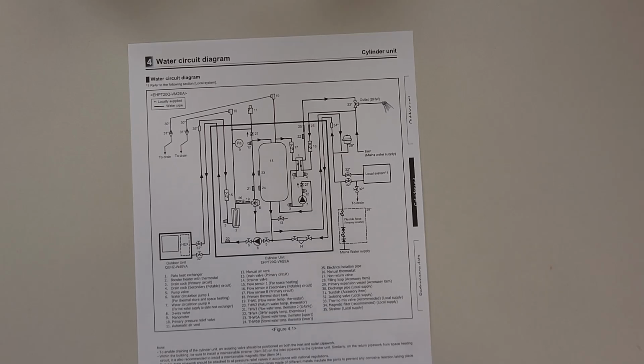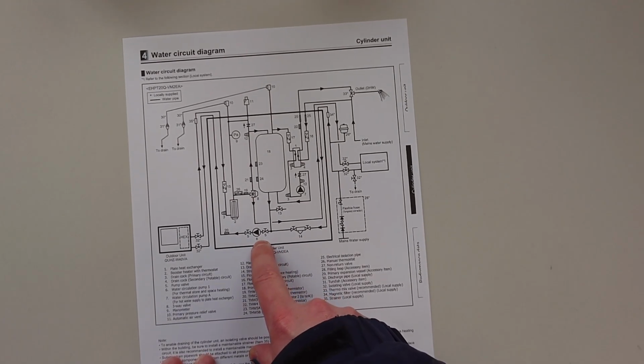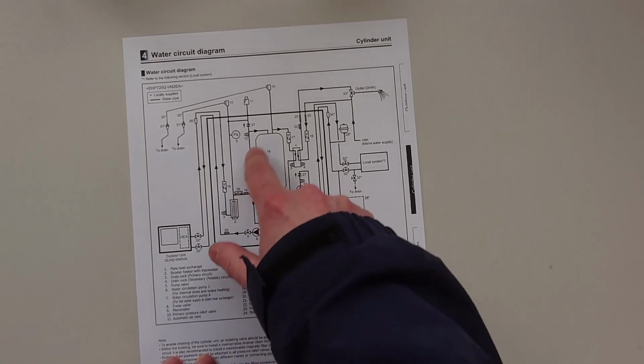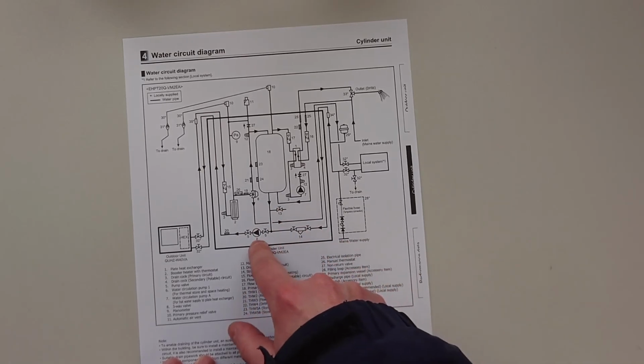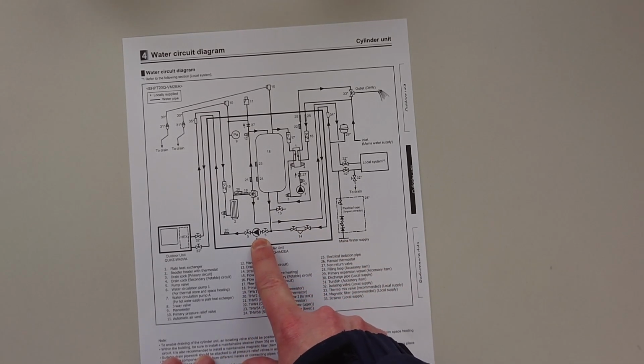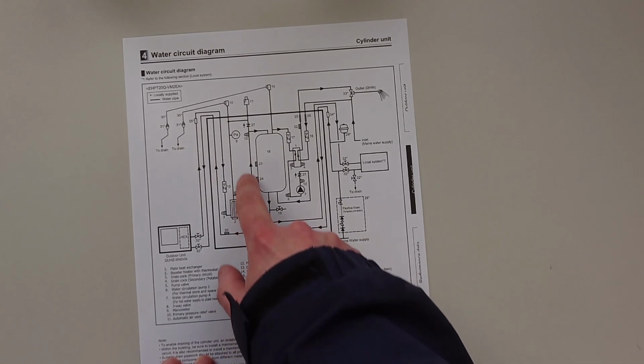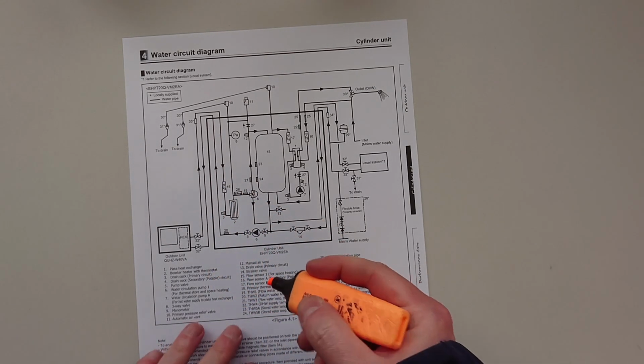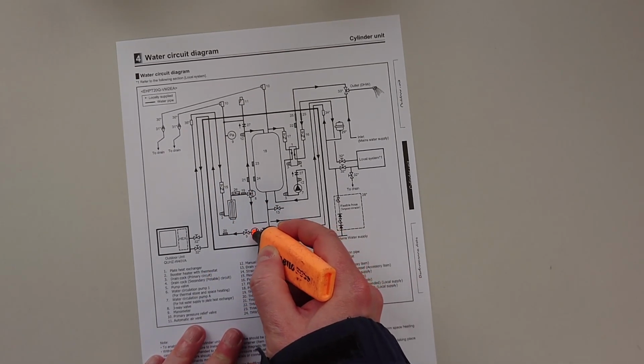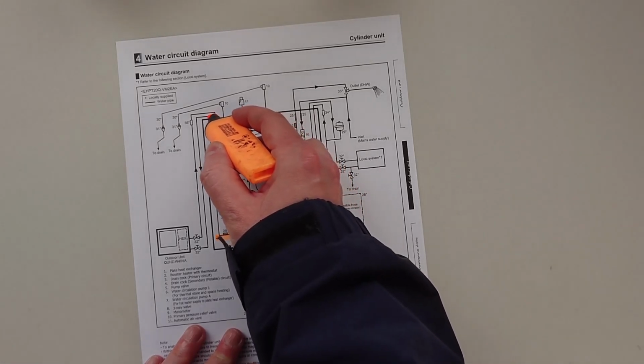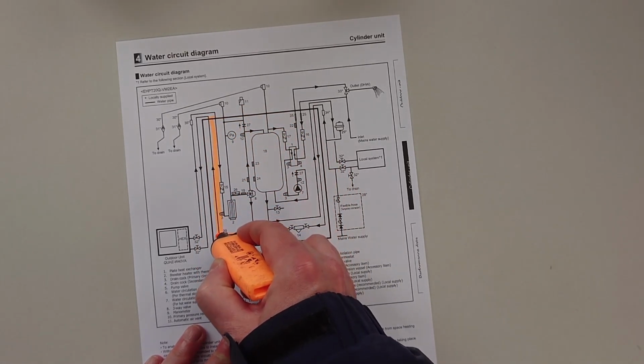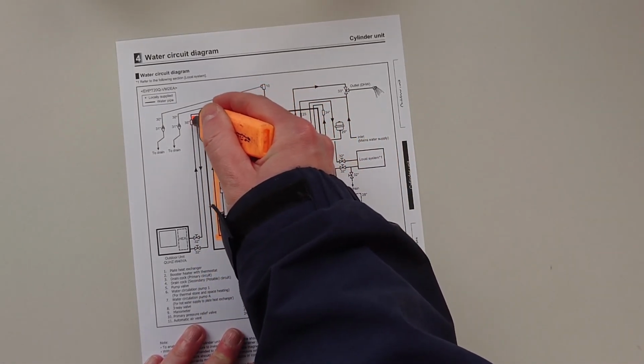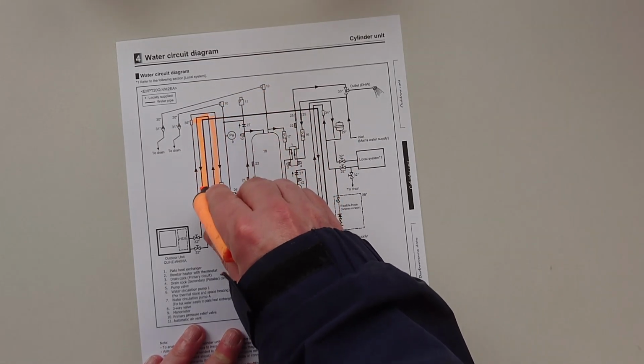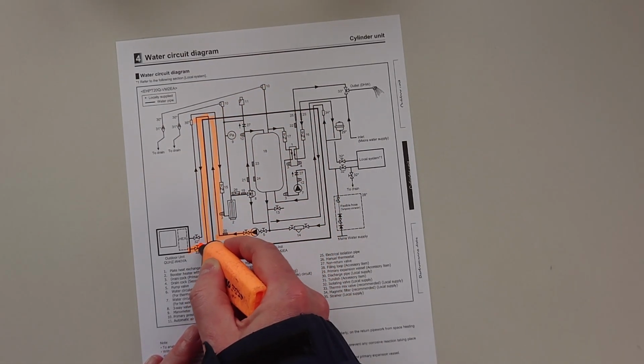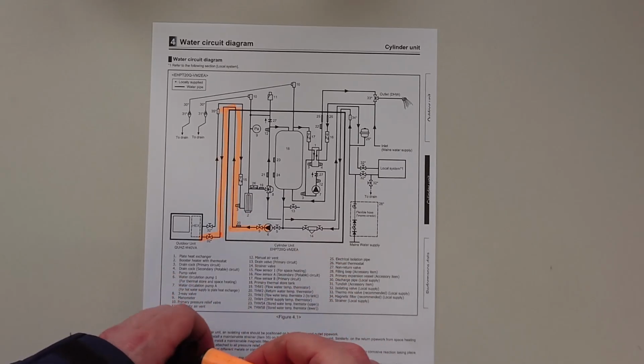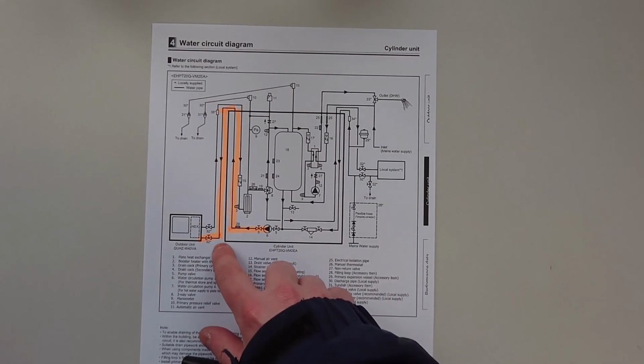So what we're going to do is start here at this number 6. All these bow ties are just valves. There's nothing scary about them. We'll start with 6, which is the heater pump. It's some sort of pump anyway. It does the heating circuit on this particular system. So initially we start the pump and we go over here on this pipe and up there, out, down here and into your heat pump, and that's an isolating valve that you're supposed to put on your local circuit.